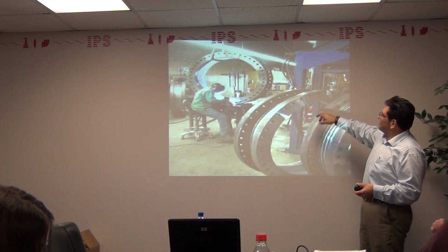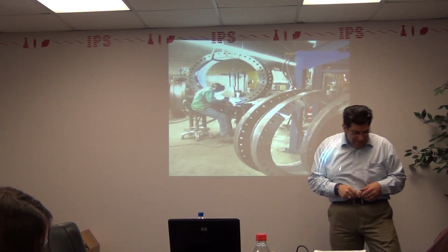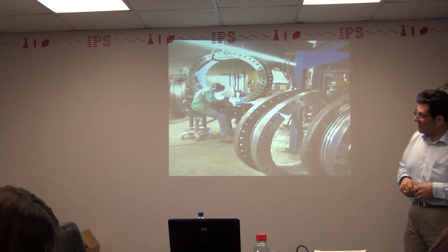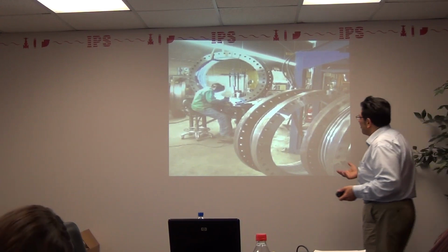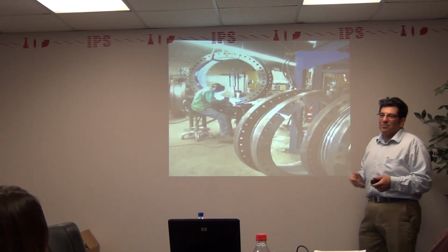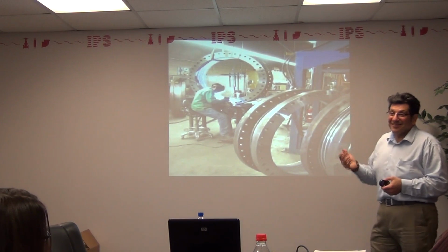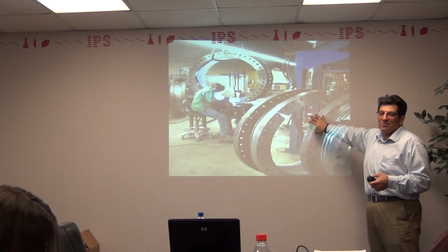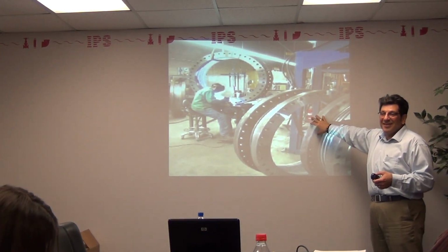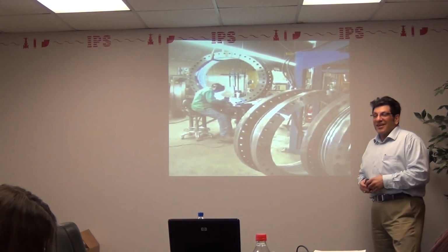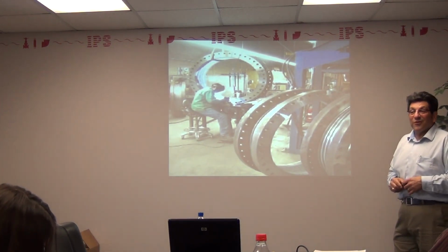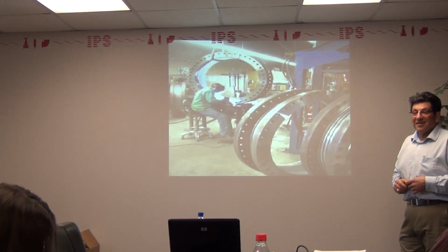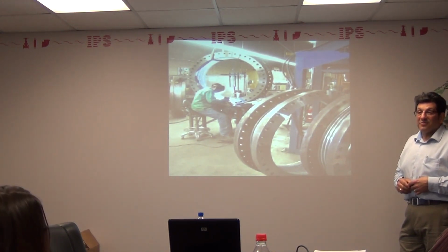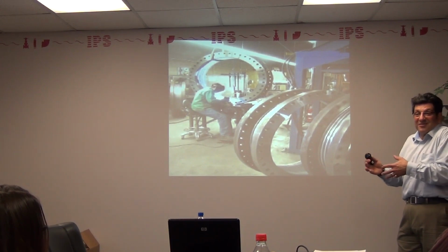So all these flanges, I was on a teleconference with London, their engineer who did this. I said, not for nothing, it's a chilled water system, I think you're going to operate at about 70 pounds, a little overkill with the flanges. They're 600-pound API flanges, 48 inches. He said that's not up for debate, that's what they use for that size pipe in the Middle East. Those are what's around, so they just have those size pipes. If anything ever went wrong or anything you're going to connect to, it's that.